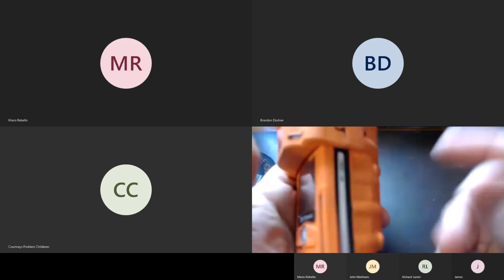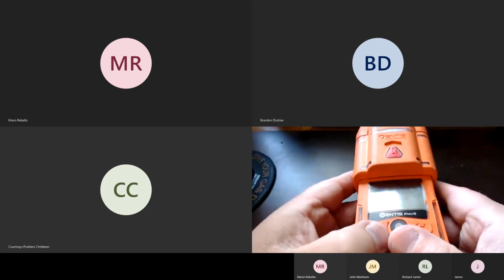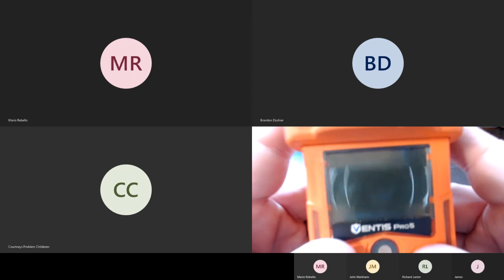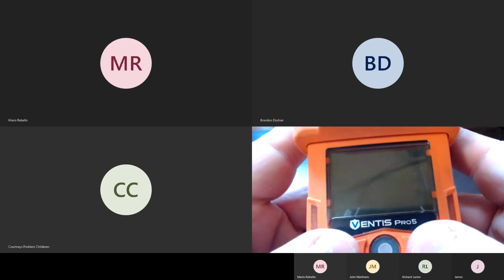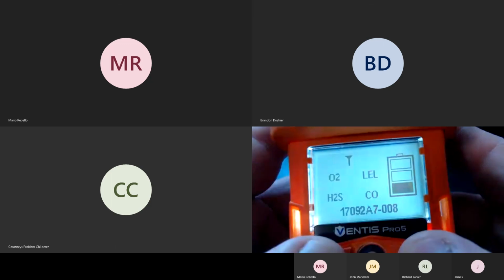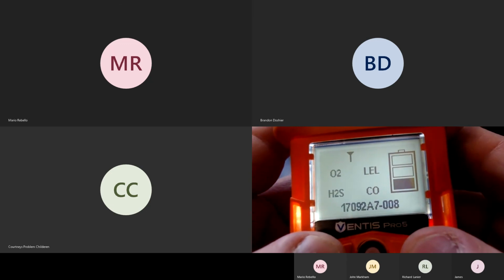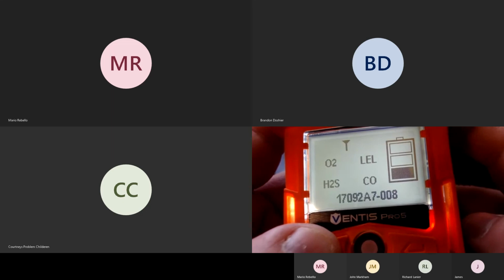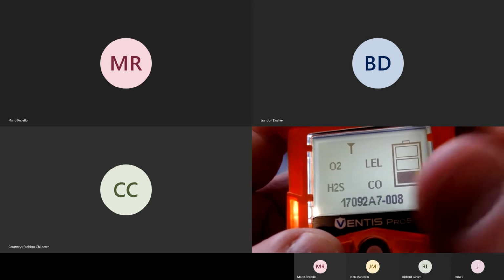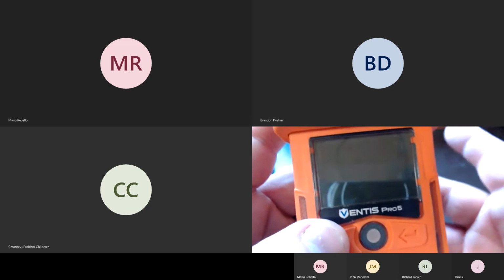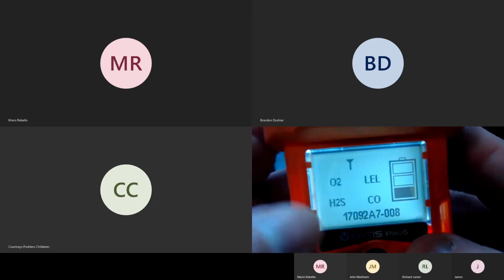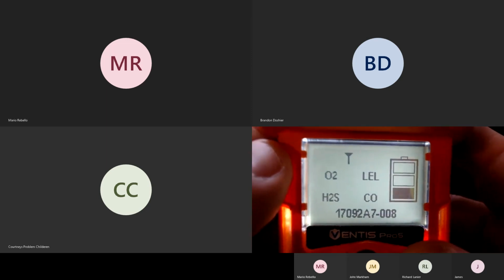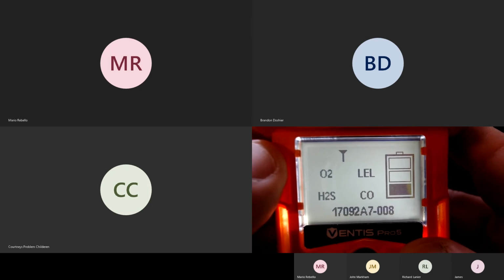Now, you might be saying, wait a second, we're firemen, we're rough and tough, and that sticker is going to get worn off after 2 months or something. How do we get that serial number if we need it? Well, on the instrument, there's a way to get what's called the quick access screen. You press and hold both buttons together, and it will come up, and on the display it will show you how much battery life it has, what sensors are installed, and at the very bottom, it shows you the serial number. This is how you can see what's going on with your instrument without having to fully turn it on. So like I said, you just press and hold both buttons together. It comes up with the quick access screen, shows me my sensors that are installed, and my battery life. Okay, this one needs charged.